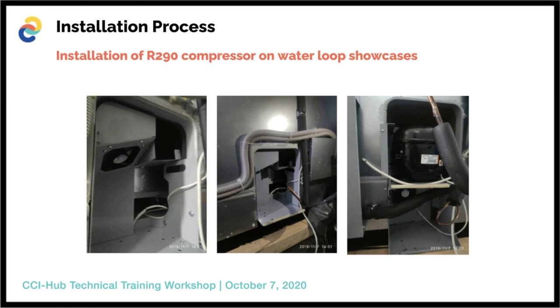The cabinets have three compressors. Actually, if you look at the cabinets, you can see three compressors with three separate circuits, especially on larger capacity units like upright chillers and glass door freezers. In self-contained equipment, the compressor is only one, the same as R290 compressors. The controller we use in these systems is the Carel MPX Pro controller with three electronic valve regulators, and it works as a capacity regulator system for a more energy efficient system.